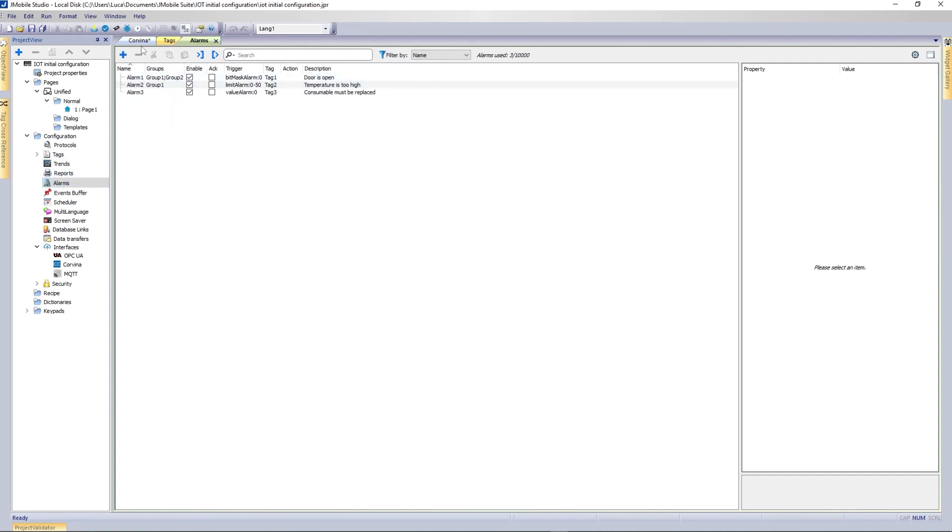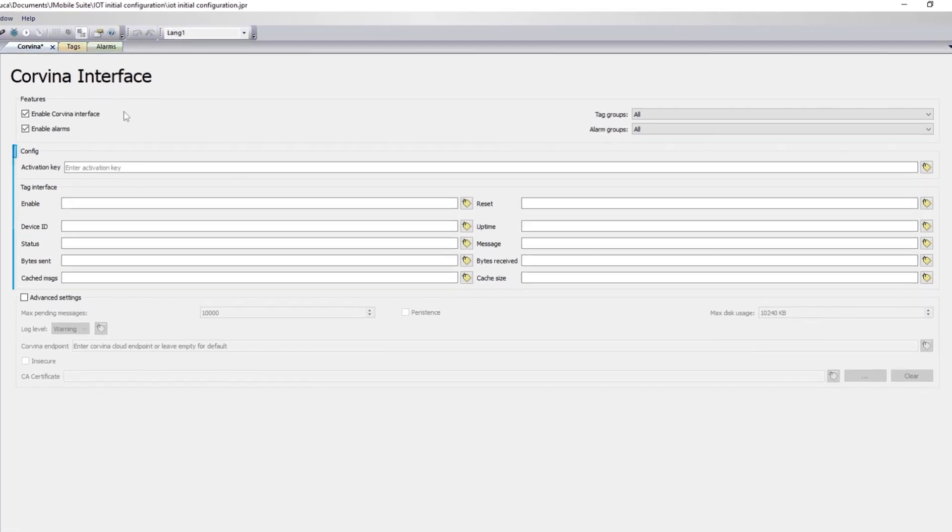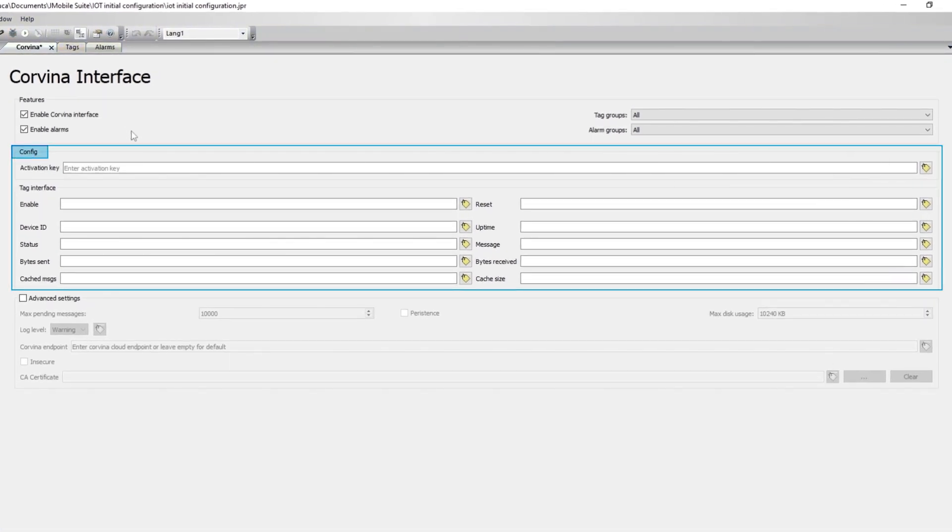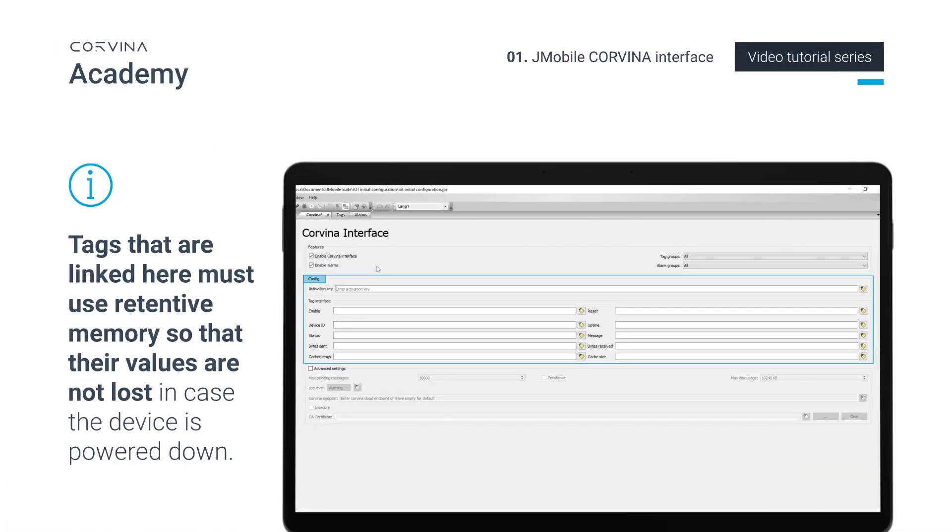All other configuration parameters can either be entered here or their values can be linked to tags so that the configuration can be set at runtime instead. Tags that are linked here must use retentive memory so that their values are not lost in case the device is powered down.